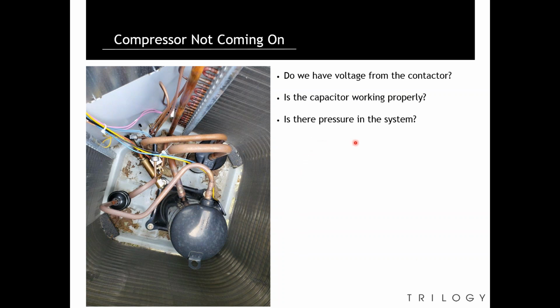Is the pressure in the system? Again, you have a pressure switch. You want to make sure we have pressure in the system. If you have the correct voltage, the 24 and the 240 volts, and the compressor is still not kicking on, or the fan is still not kicking on, try using a hard start. Now, if you're going to use a hard start, remember, you can only keep those on there for 48 to 72 hours. It is not permanent. We want to take those off. They can start a fire.